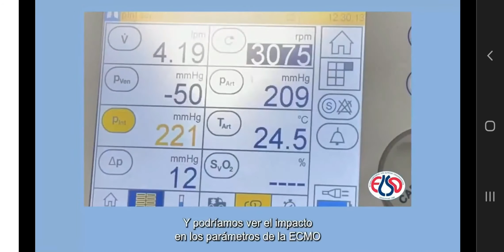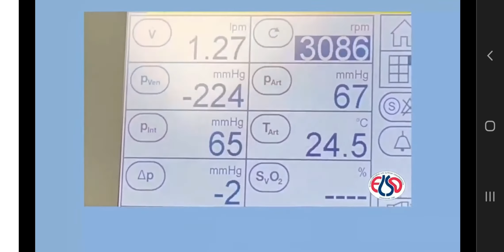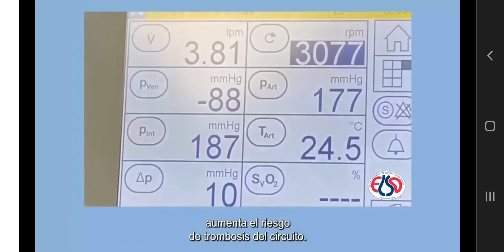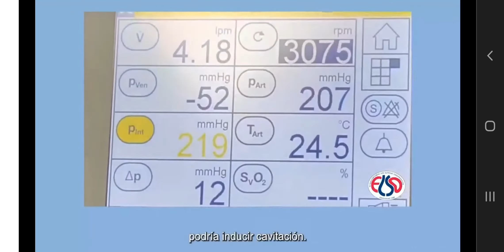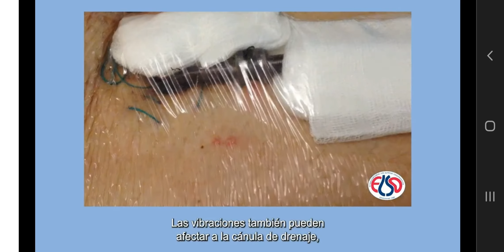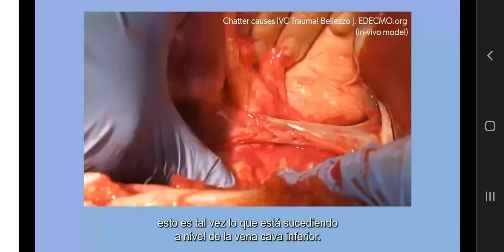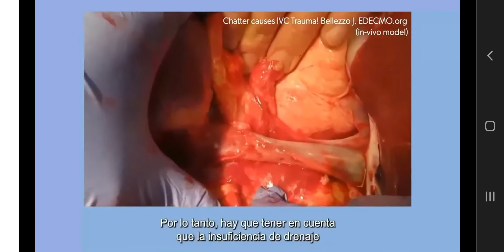And we could see the impact on ECMO parameters in this other video. The temporary collapse of the venous vessel generates an inconsistent, erratic blood flow, like in this case, and this persists until the issue is solved. This might impair ECMO support, and moreover, this reduction of blood flow increases the risk of circuit thrombosis. The inlet pressure becomes inconsistent, decreases, then increases, then decreases again, and if the inlet pressure becomes really negative, this might induce cavitation. Vibrations may also involve the drainage cannula, like in this case, and if this is what you could see at the bedside, this is maybe what is going on at the level of the inferior vena cava, so consider that drainage insufficiency might potentially induce vessel injury.